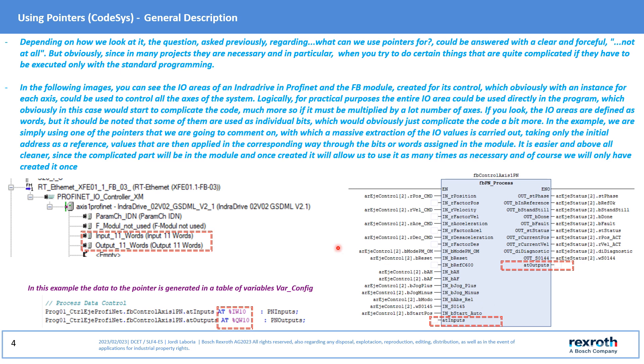All of these added directly to a module would complicate the program incredibly, taking into account that this same operation should be repeated for each of the IndraDrives or elements that we are using. The FB itself already contains all the necessary data for the established functionality and allows it to be used in indexed form for all similar equipment in the installation, which obviously leaves the program cleaner and clearer since it is inside the FB where the movement of the words or deactivation of the bits is carried out. The pointers play a fundamental role since they allow us to access without great complications the areas where IndraDrive I/Os are located in the example. In the example, one of the pointers that we will see in the video tutorial is being used.